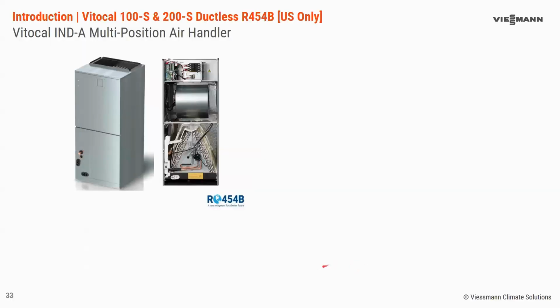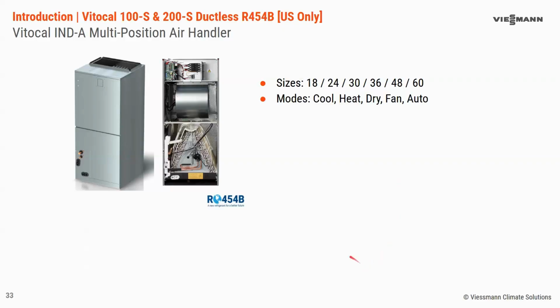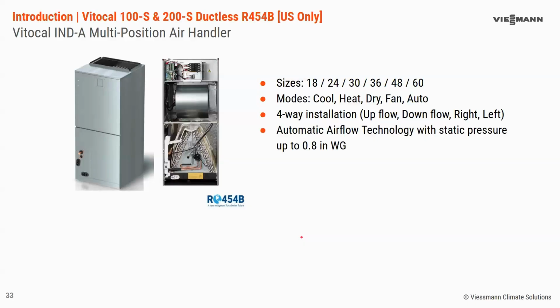And the last indoor unit for ductless is the multi-position air handler. So that comes from 18,000 to 60,000 BTU. However, I'll call out that the 36 through 60 is for the light commercial. A little more to come there on that. Standard models, 4-way installation. The blower motor will adjust automatically, called automatic airflow technology, up to 0.8 inches of static.